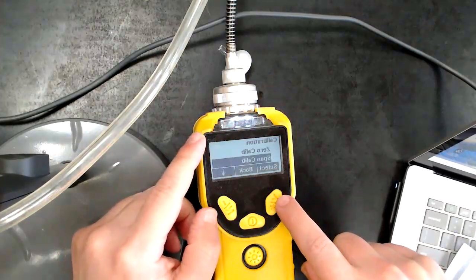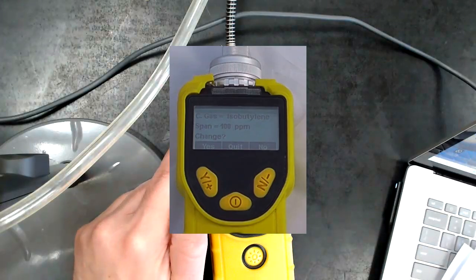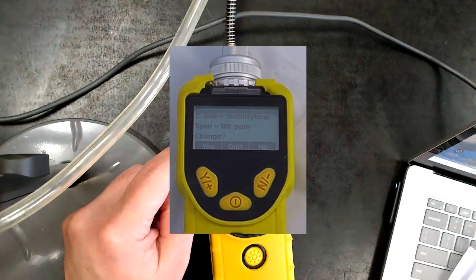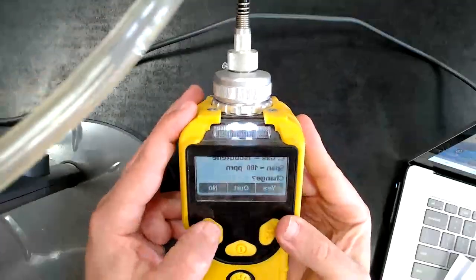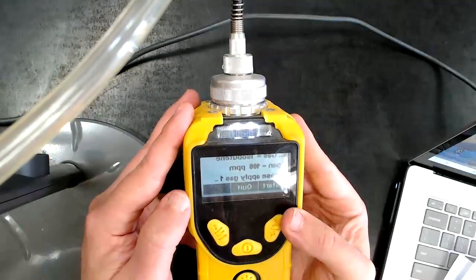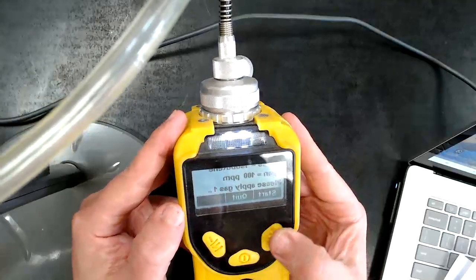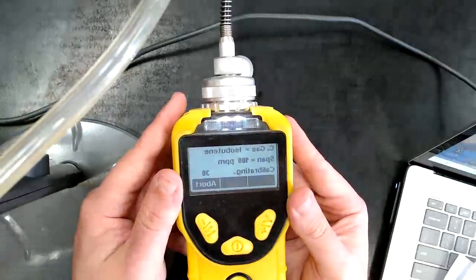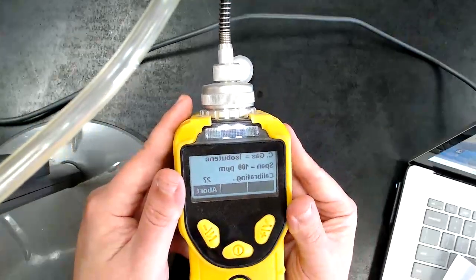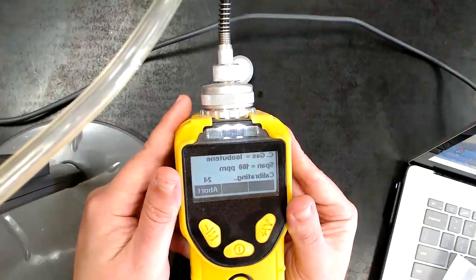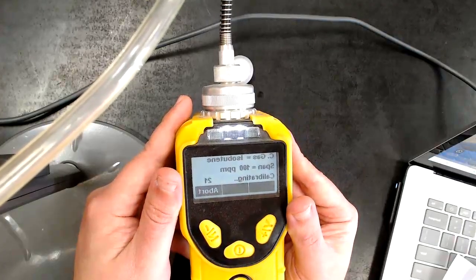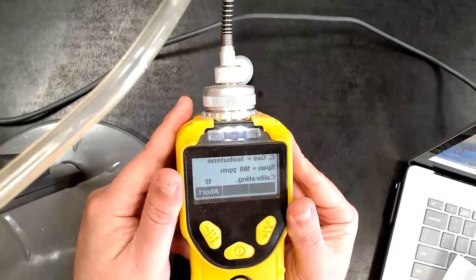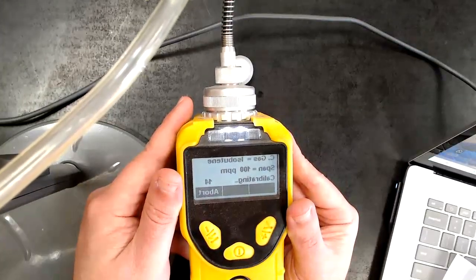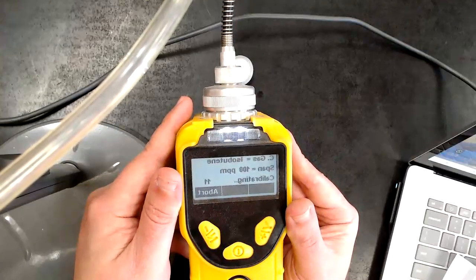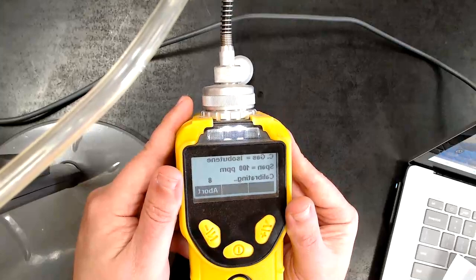Then we select the span calibration for the 100 ppm. We have the isobutylene in there. It asks if we want to change the setting, and we want to keep it. Please apply the gas. We've already applied the gas, so we'll start. Now it's calibrating. One thing: usually it goes by ppb. Remember, 100 ppm is 100,000 ppb. That's how it wants it when you're entering it.